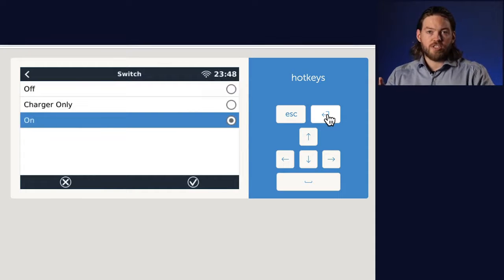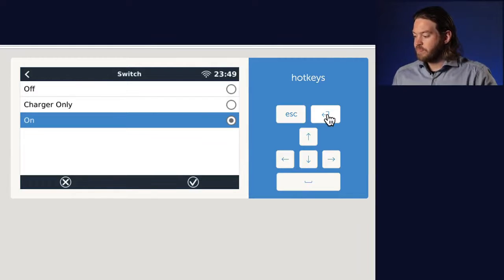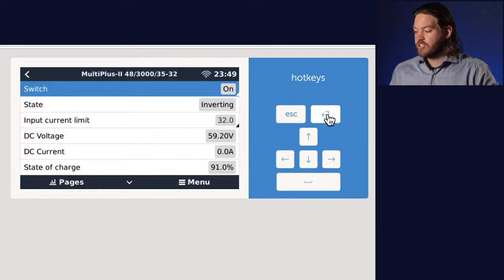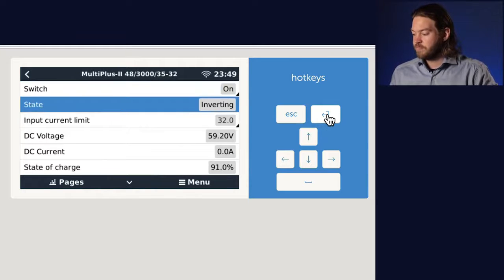Once these units are each connected to each other like this, switching their physical hardware switches on and off will cause an error to form on the system. Each of the units is synchronized, and if one of them is lost, presumably the system thinks there's a problem or a fault, it'll report that error through the GX device or to the VRM portal and say, hey, I'm missing one of the other devices in my system. If you wish to switch the unit off, they have to be switched off in a synchronized way. This can be done through a GX device, or you can also run an assistant to switch off with an external control. In this case, I'm going to leave them on, but that's the way I'd turn the system off if I wanted to, through this software switch.